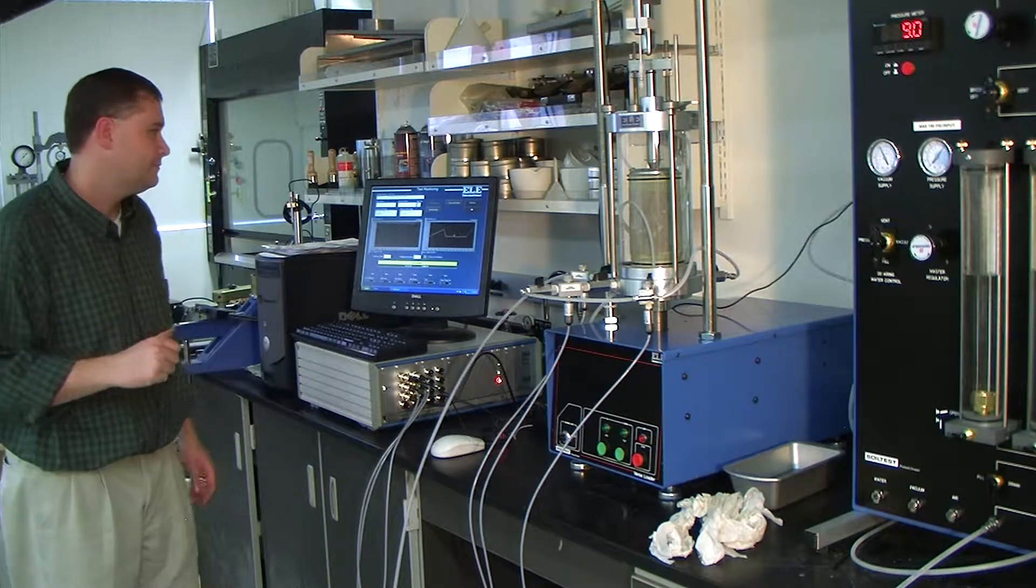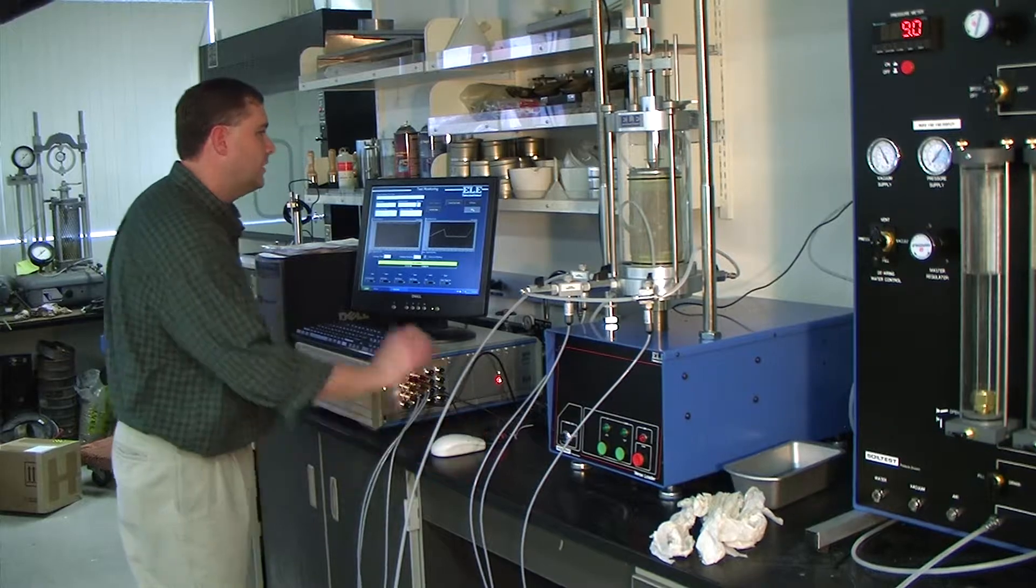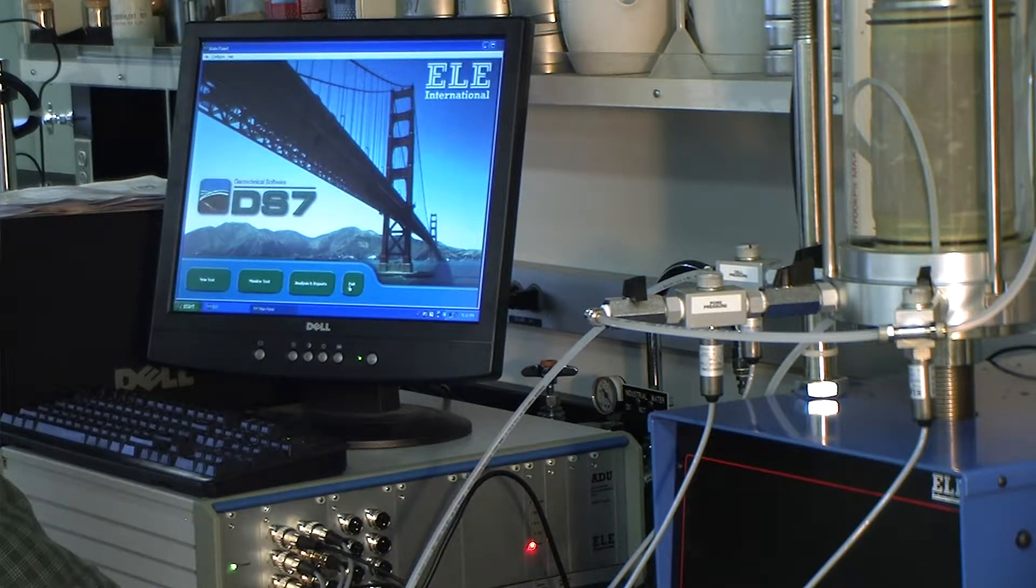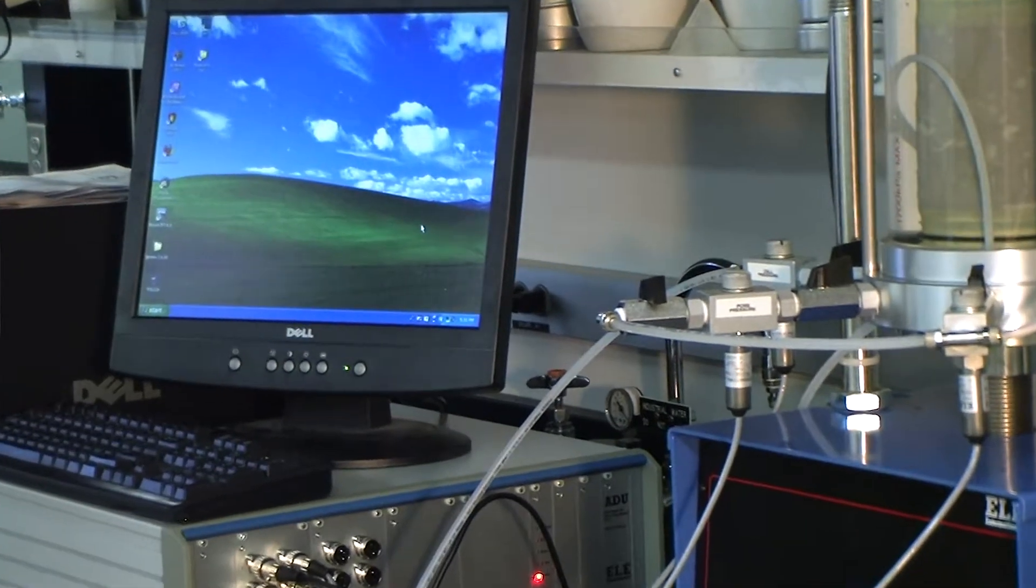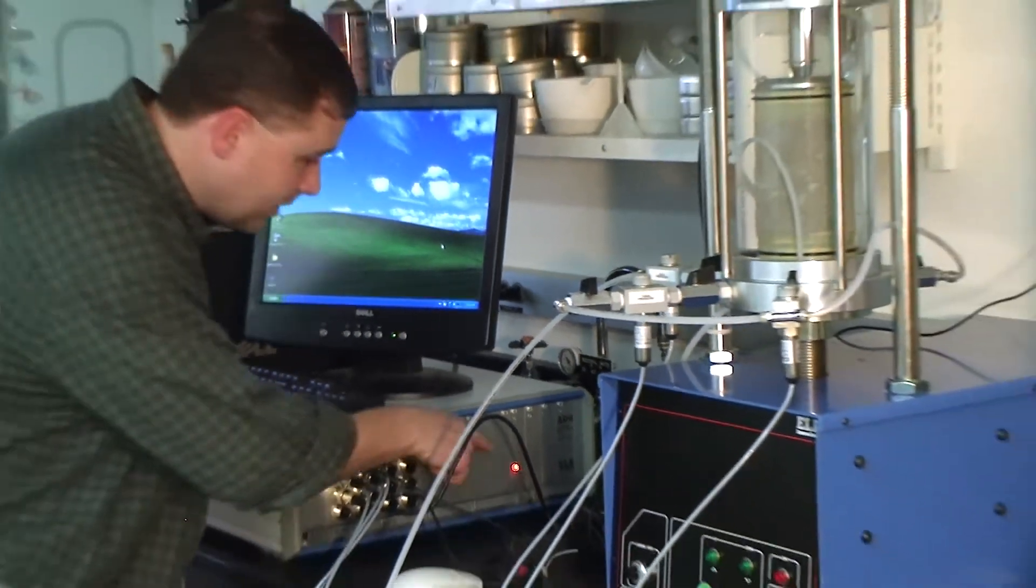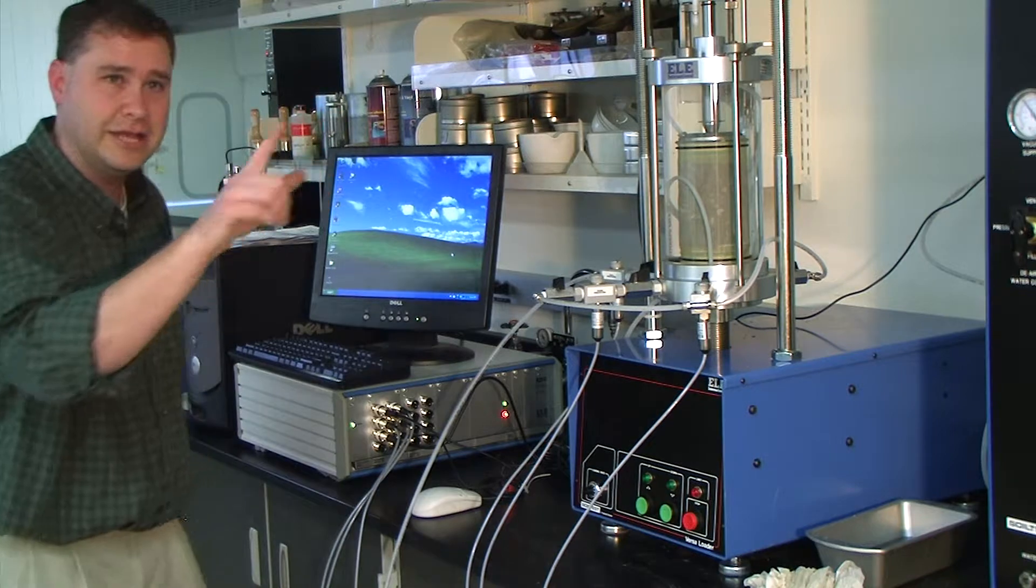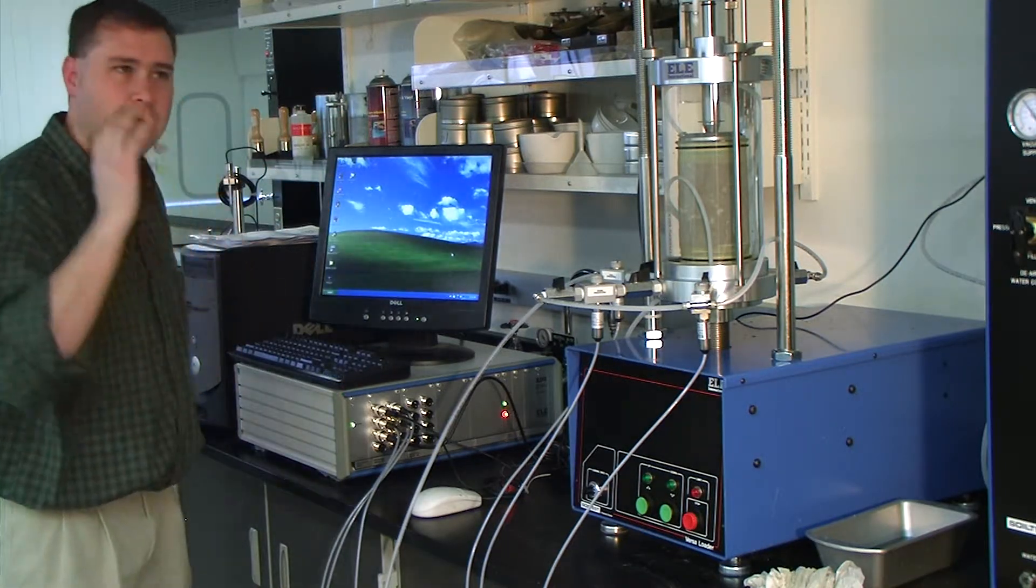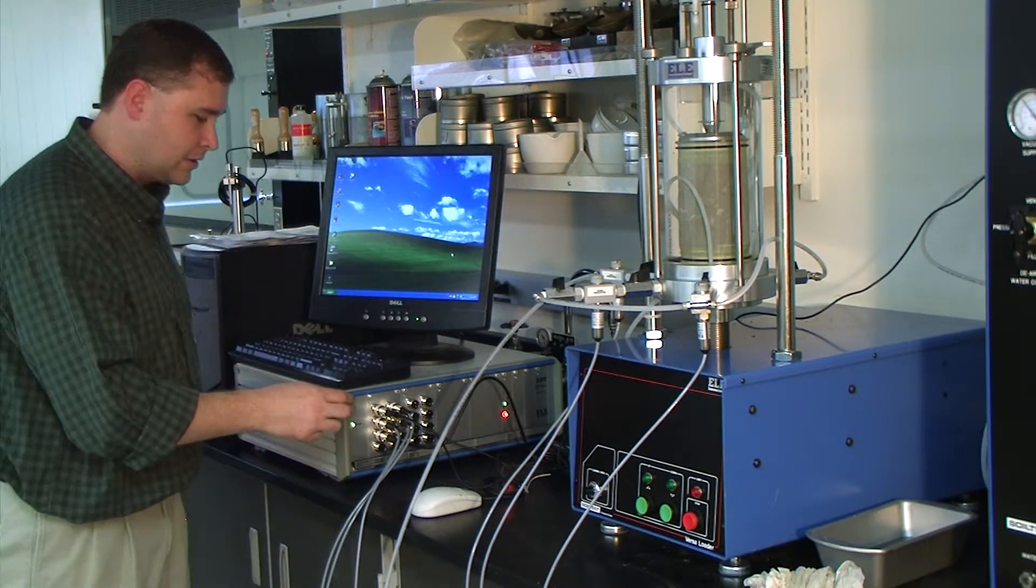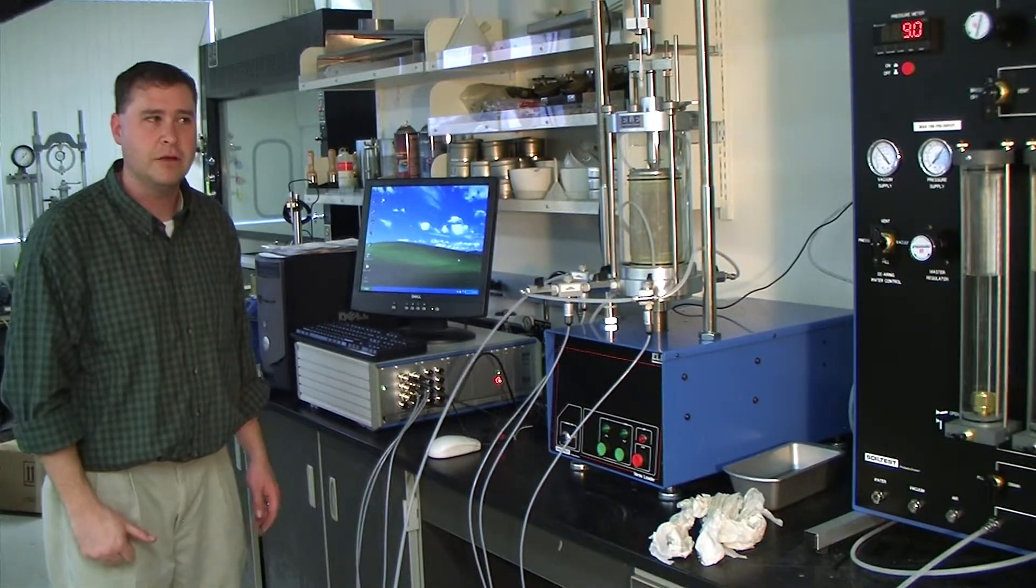And if you want to leave it overnight, you don't have to have this on here. You click OK. If you click OK, it's still recording data. Go back to the main screen. You can go to exit. Get out of DS7 completely. You can turn the computer completely off. As long as you keep the power to the ADU on, keep that test running, and you have that scan light, this convert light flashing. You're always monitoring data and checking data. And then tomorrow morning, or the next day, or three hours from now, you can turn everything back on. The ADU will communicate with the software, download all of that data that's recorded, and you can check and see where we are. We'll do that next.